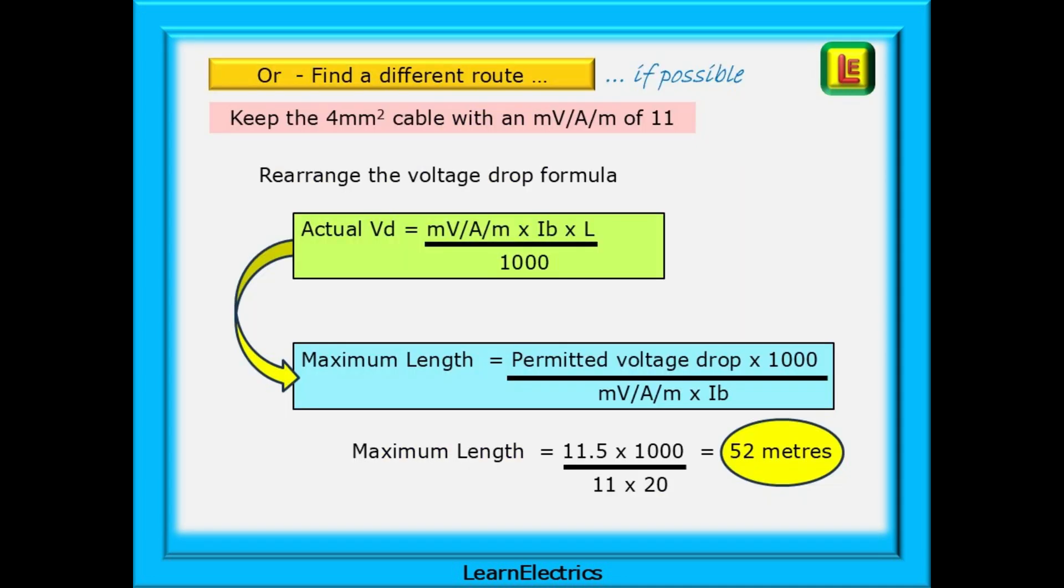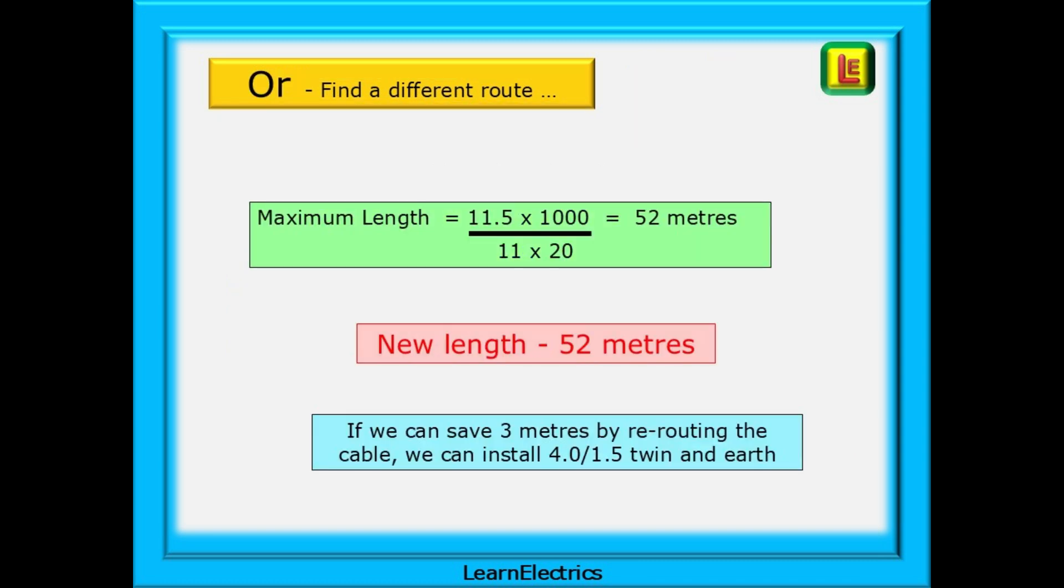Or we could keep the 4mm cable and try to find a shorter route that is still acceptable. To do this, we need to rearrange the voltage drop formula to make the maximum length of the subject. We've done this for you as shown in the blue box. The maximum length is found by multiplying the maximum permitted voltage drop by 1000 and then dividing this by the millivolts per amp per metre and the design current IB. Putting the numbers into the calculation as shown, we have an answer of 52 metres. So, the new length is 52 metres compared to the previous 55 metres. If we don't need 55 metres, then don't use it. If we can save 3 metres by re-routing the cable, we can still install 4mm by 1.5mm twin and earth.